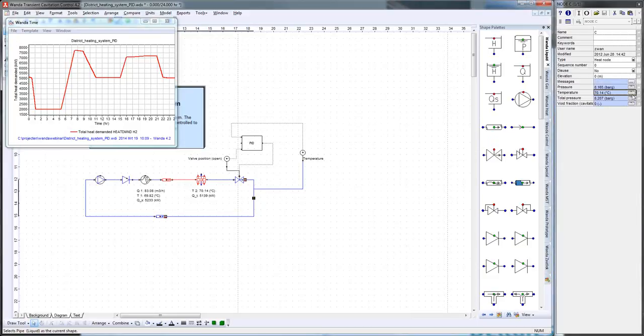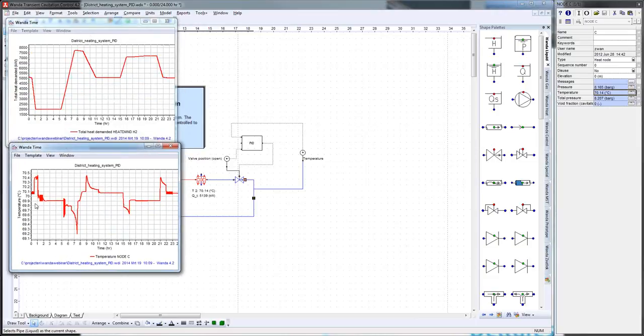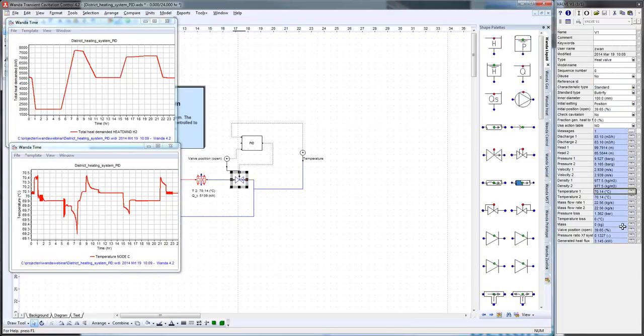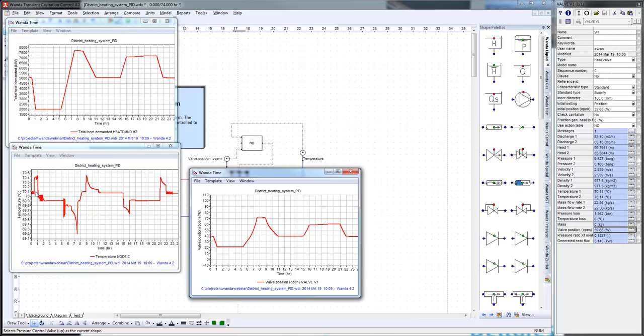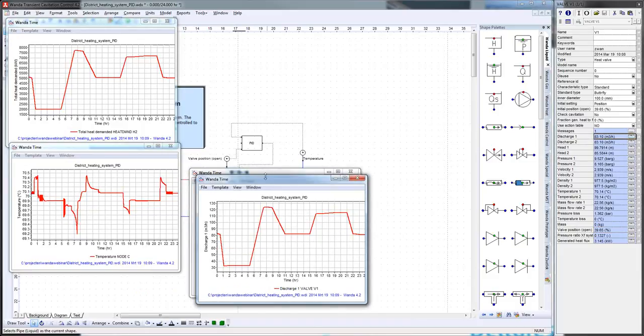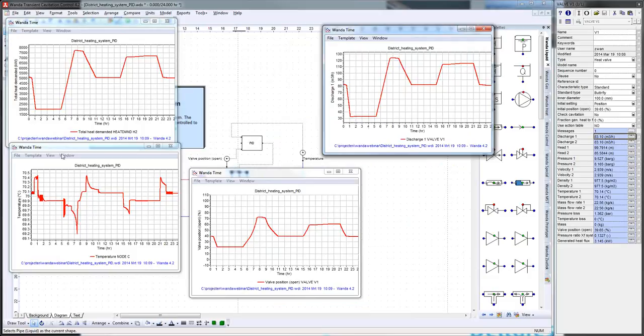Let's first have a look at what's happening at the temperature. You can see overall it stays nice within the boundaries. At the moment when there is a decrease or increase, of course there's a jump in temperature and you have some reaction time for that, which is logical. Now if you look at the valve position, you can see for example here, when the heat demand drops, the temperature increases, the valve starts closing, and the discharge is dropping. You can also see the discharge going down. In the morning it increases and then the valve needs to start opening - and you see it happening. So this system works nicely.